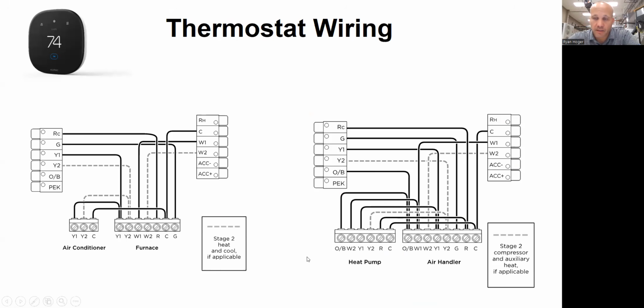split system, and the indoor air handler has gas heating with it, and the outdoor unit is cooling only, right? So we're more like this scenario on the left, I guess you would say. This thermostat needs to know the outdoor air temperature. In the case of the ecobee, like I'm showing up in the corner, ecobee gets the outdoor air data from the internet, from your zip code. So it finds your current outdoor air temperature. The other option is you can get a thermostat like a Honeywell or Venstar or somebody that has an outdoor air sensor that wires to the thermostat. So you'd have two more wires coming into the thermostat. There'd be more terminals on here, right? For outdoor air temperature. And now we go to an outdoor air temperature sensor outside. So one way or the other, the indoor thermostat needs to know the outdoor air temperature.